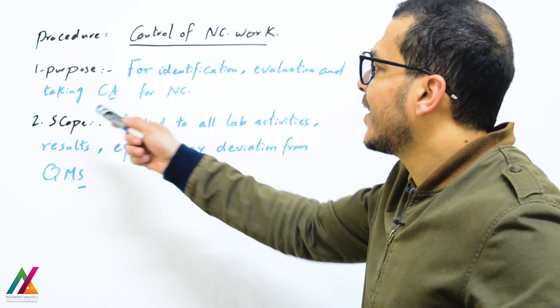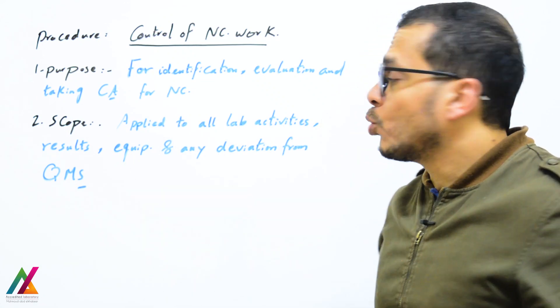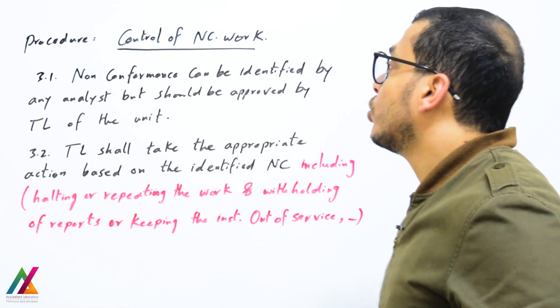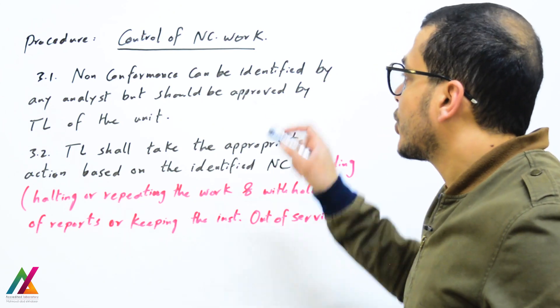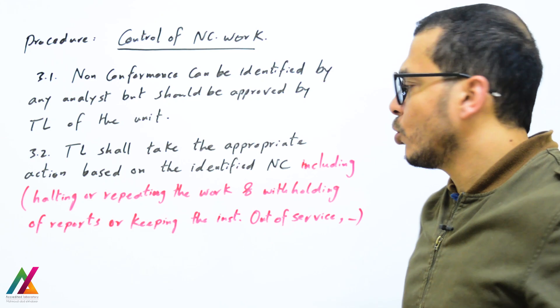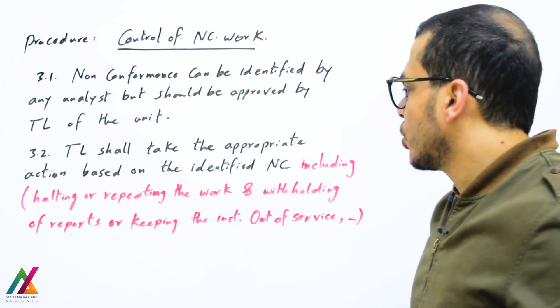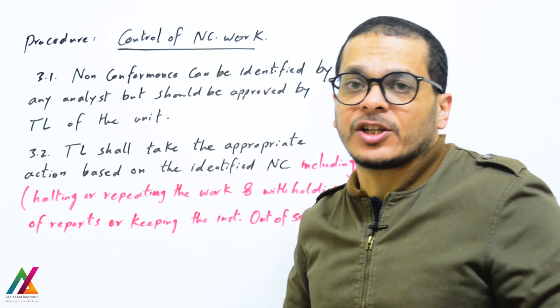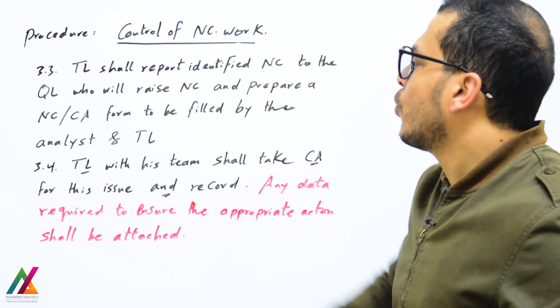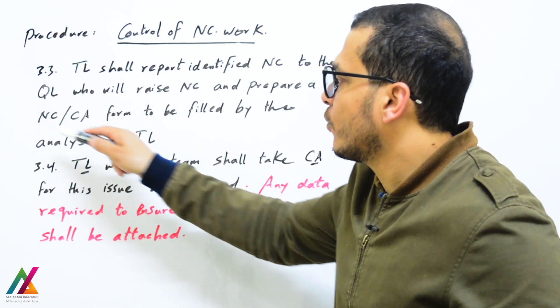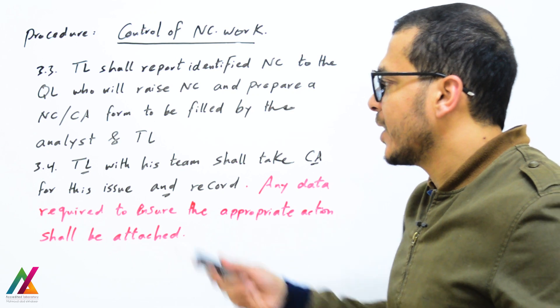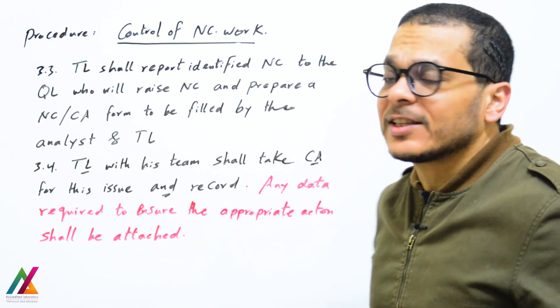The non-conforming work procedure — control of non-conforming work — has the purpose of identification, evaluation, and taking corrective action for non-conforming work. Its scope applies to all activities, results, equipment, and any deviation from the quality management system inside the lab. In the procedure: non-conformance can be identified by any analyst but shall be approved by the technical lead, who shall take appropriate actions such as halting or repeating the work, withholding reports, or keeping equipment out of service.